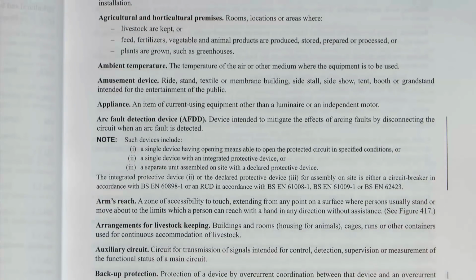So just like if you buy an RCD, you can buy an RCD as a separate item that doesn't include overcurrent protection. You can also buy an RCBO, which includes both overcurrent protection and residual current detection. A similar arrangement applies here - it's really a question of checking what you're buying and buying the appropriate device or devices.